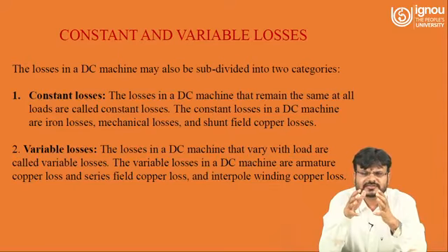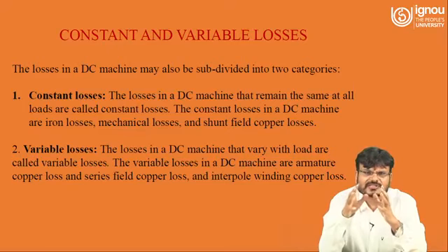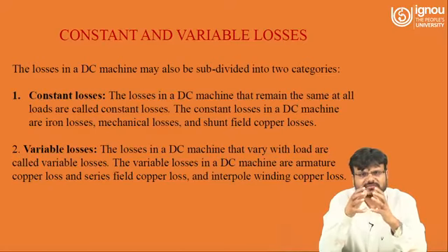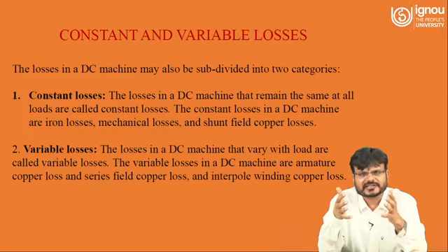The constant losses are what? These losses don't depend on the load, right? Or you can say these losses are fixed and cannot be changed. They are the iron losses, that is eddy current losses and hysteresis losses, mechanical losses, and shunt field copper losses.